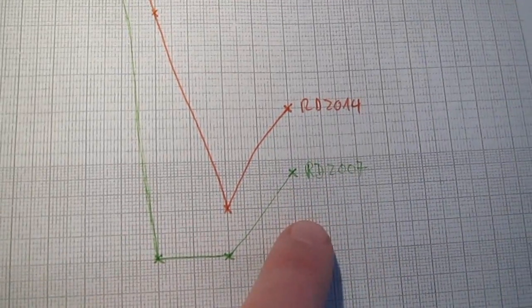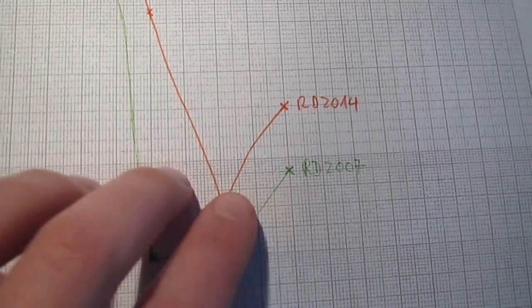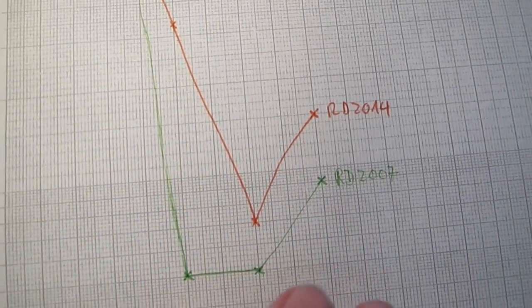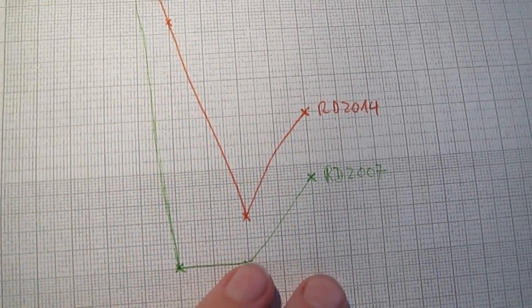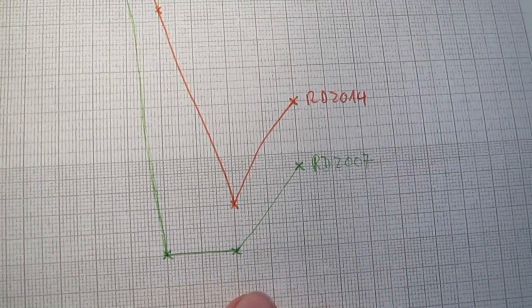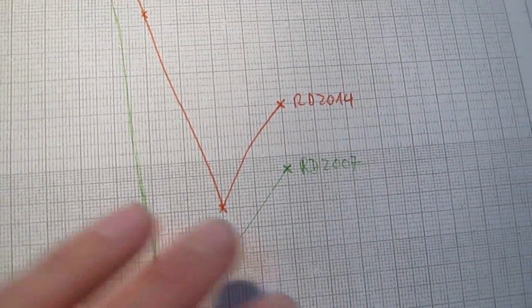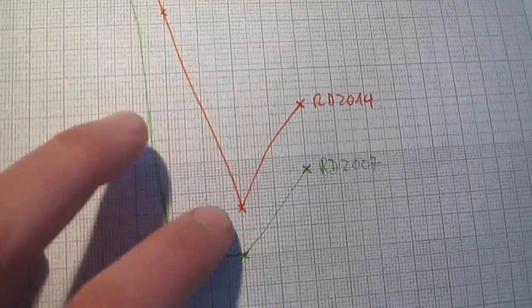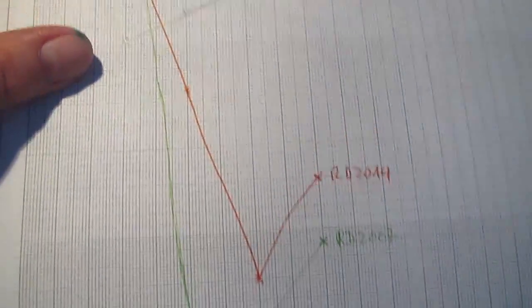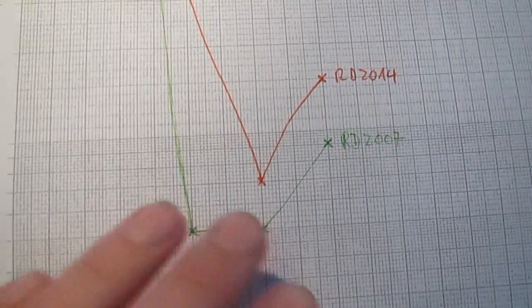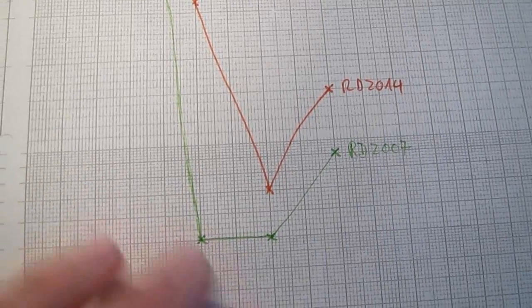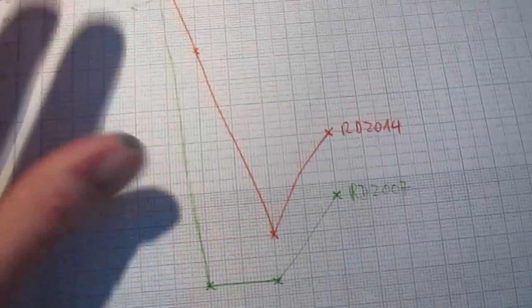This is probably due to Compton scattering, because as I said I used a large field to measure both these detectors. And at 100 kV probably Compton scattering, and thus a lower energy photon and pretty much beta radiation or electrons, were detected to a greater extent than at lower energies. This would explain that in theory, but I didn't have time to conduct more of these tests. So probably I'm going to repeat it again at some other time and measure with more different energies like 40 kV, 45, 50, and so on, and not just in steps of 20 kV.